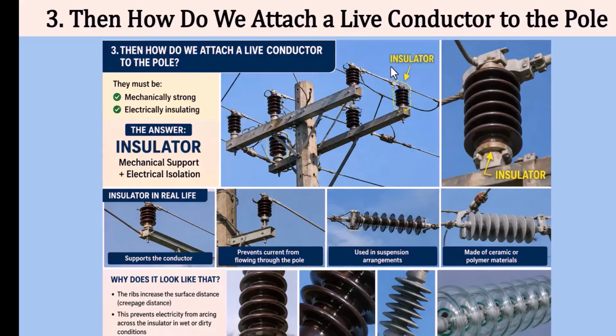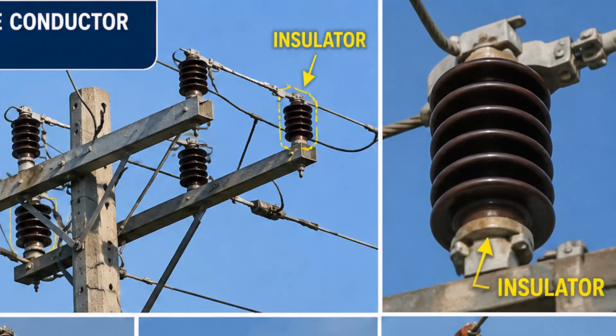It's called an insulator. An insulator has two extremely important responsibilities: mechanical support and electrical isolation. Mechanically, it supports or positions the conductor. Electrically, it helps prevent the energized conductor from forming an unintended current path through the supporting structure. But now look carefully at the insulator. Why does it look like that?